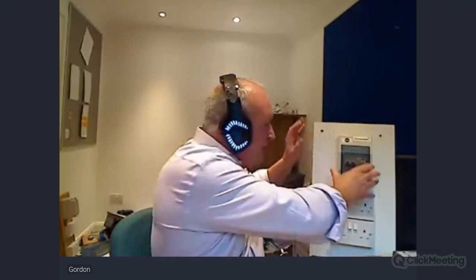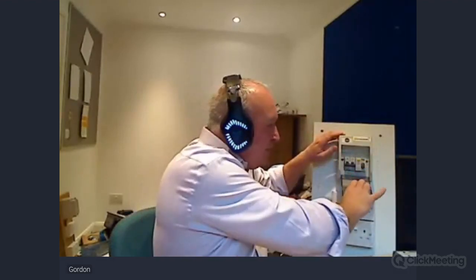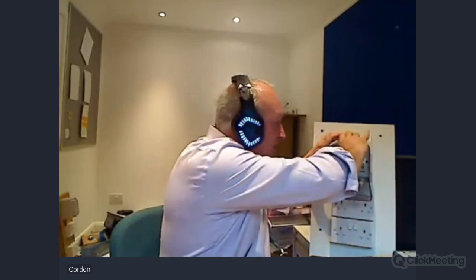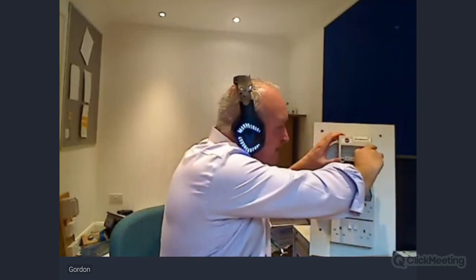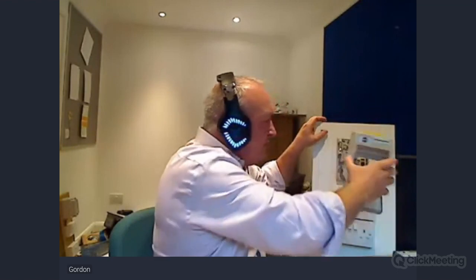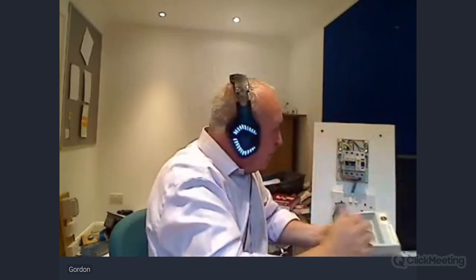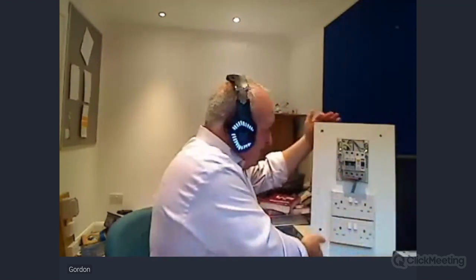There's my board supplying a little 2-socket radial circuit. In most instances, we would actually padlock this off first, okay, but in this instance it's slightly tricky to do. So I'm going to take this board off. I'll bring it a little closer so we can see what we've got: an RCD incomer, then 2 circuits going out supplying these sockets.